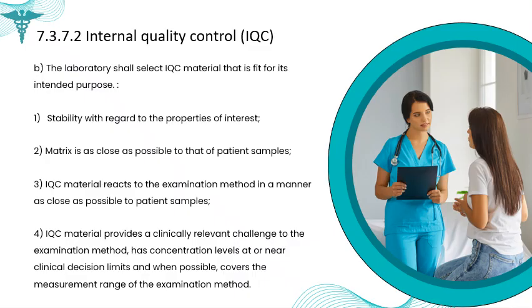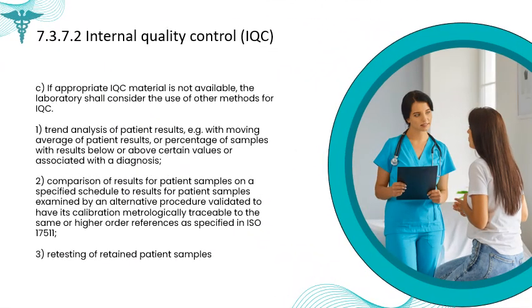that the IQC material provides a clinically relevant challenge to the examination method, includes concentration levels at or near clinical decision limits, and, where feasible, covers the measurement range of the examination method. In cases where appropriate IQC material is not available, the laboratory shall consider alternative methods to ensure internal quality control.